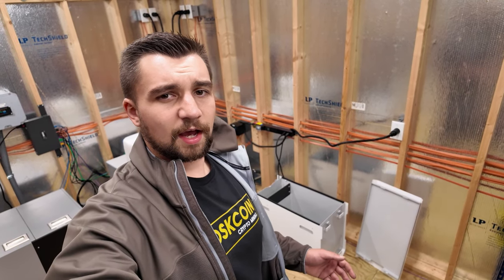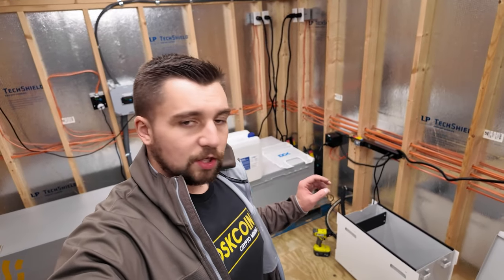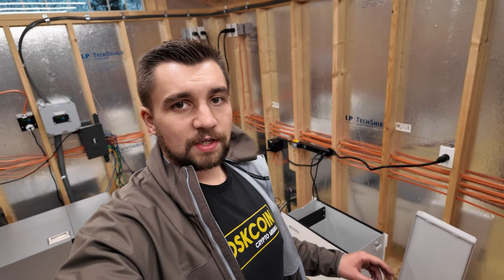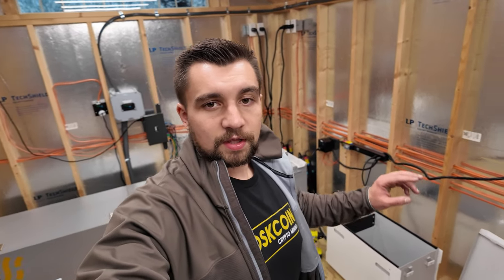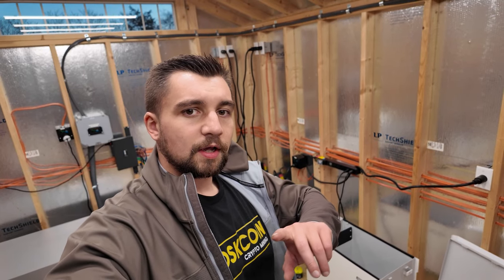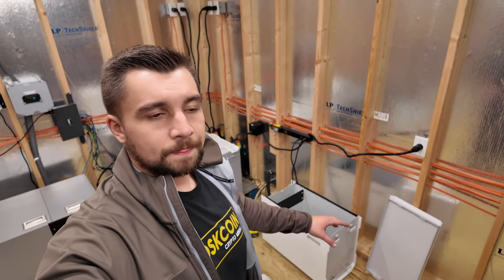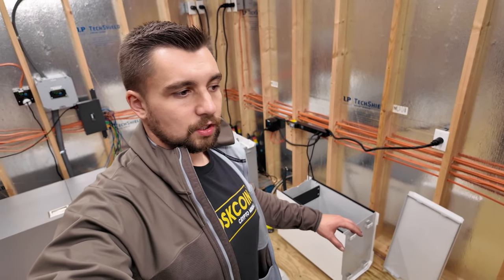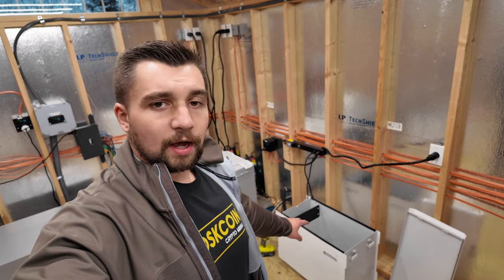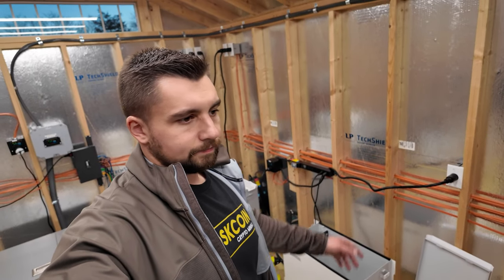We started in the afternoon on the Bitpod install. We've got the hoses through the wall where we've got them connected. At this point, we need to get coolant into the dual loop system, right? So basically the feed between the dry cooler and also the enclosure heat sink here on the back. And then we will need to get that system finished. Then we'll put 2 miners in here, fill it with immersion fluid, and that's it.